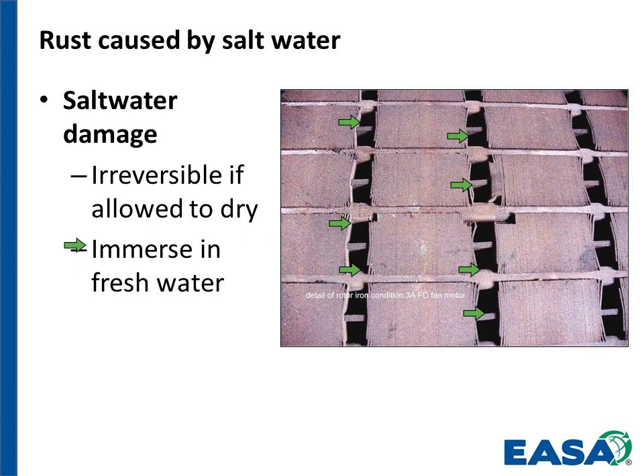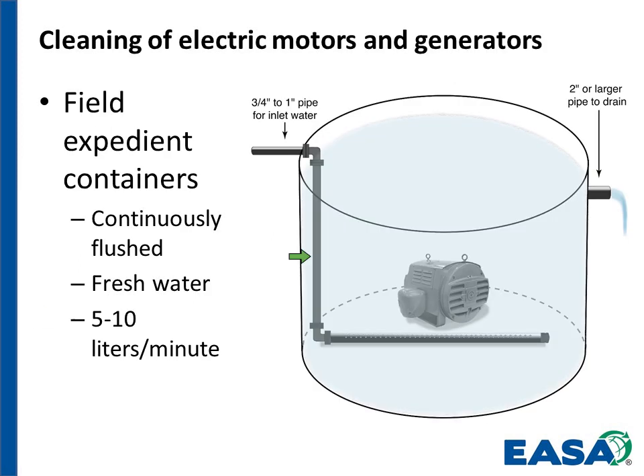So if you look at this next slide, the cleaning of electric motors and generators, this is just showing a simple tank, but a swimming pool, a dumpster, or a very large tank used for overflow chemicals that is empty and reasonably clean, anything like that you can use to place as many electric motors as possible in, and flood them with fresh water. In a perfect world, we want a water inlet so that we're circulating and pushing this fresh water through, hopefully flushing as much salt water out as possible. 5 to 10 liters a minute is a reasonable exchange of water to flush through here. Then as the service shop is able to get to the electric motors, you pull out, dismantle, pressure wash, clean, bake, and get rid of the salt water.